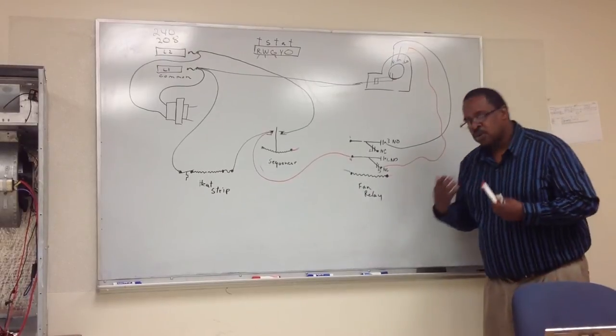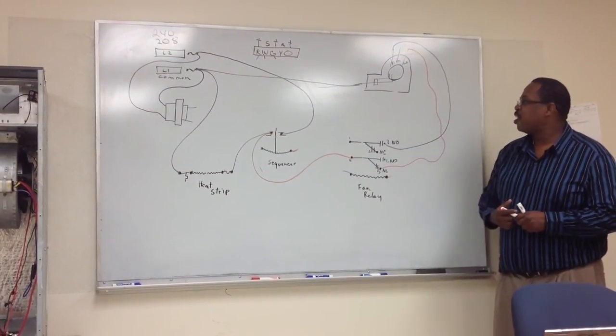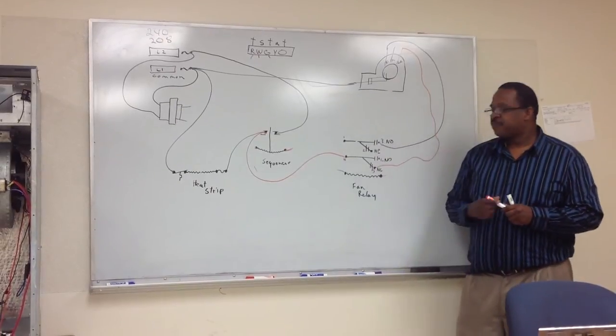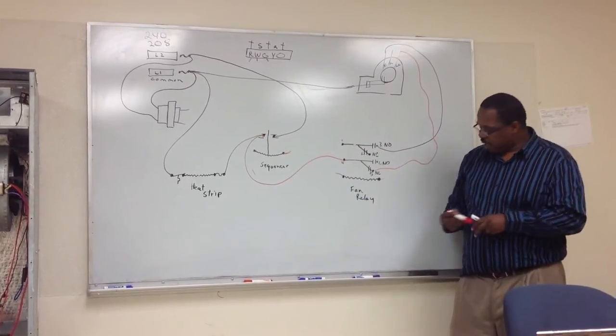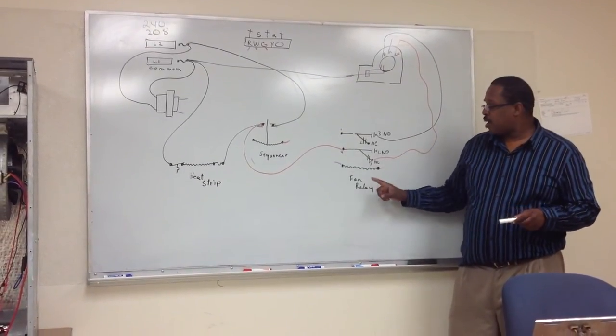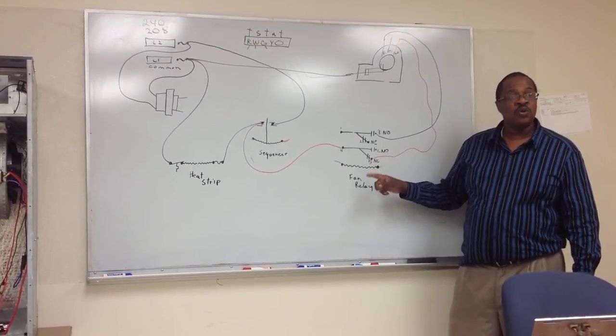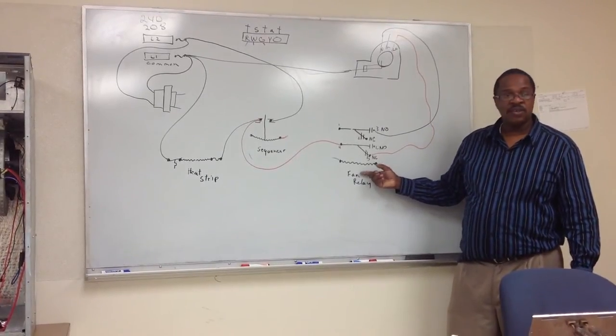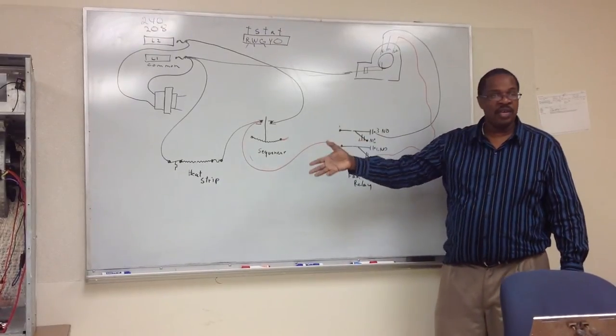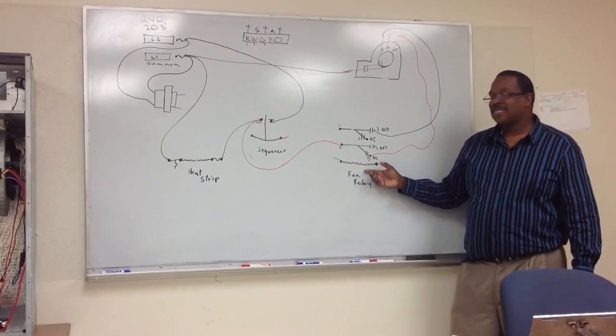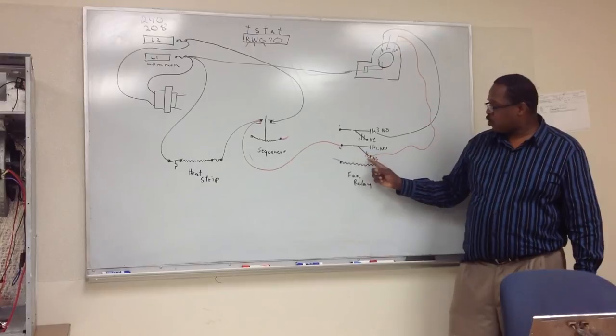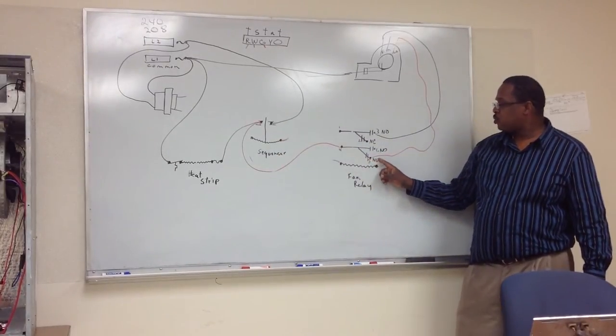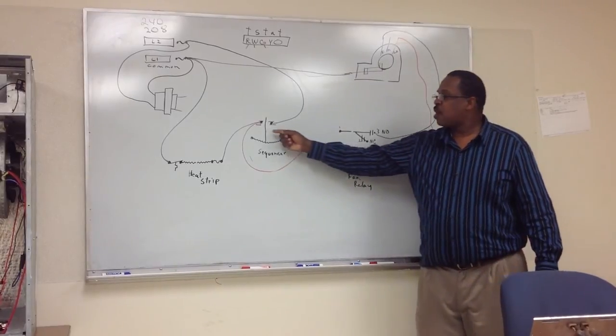Like I said, read up on these things, read your books, read up on sequencers, read up on fan relays, and this will just make you understand it even better. But to show you how to wire it up, you wire them together. Now, if we have a call for cooling or fan on, that's the only time the fan relays energize. When you have a call for cooling or fan on, or on heat pumps, when it's running in heat mode, the compressor and fan, the fan relays energize. But for electric furnaces or electric heat or emergency heat, the fan relay is not energized.